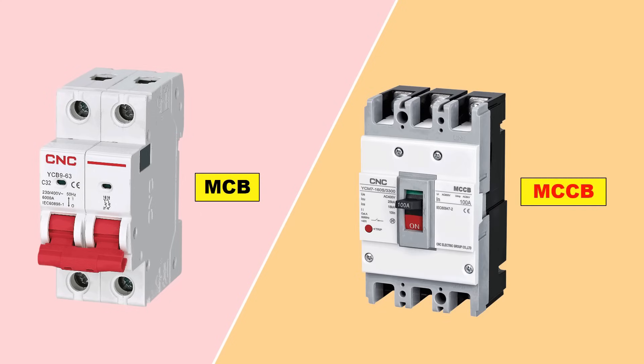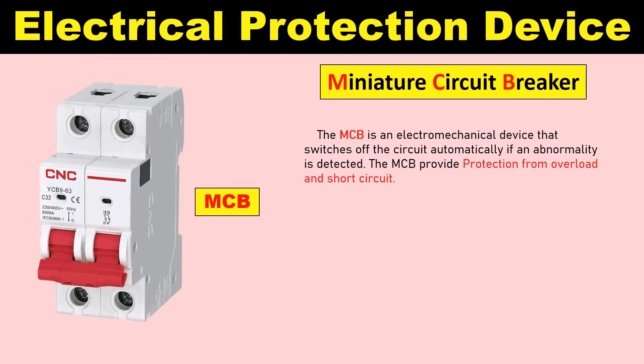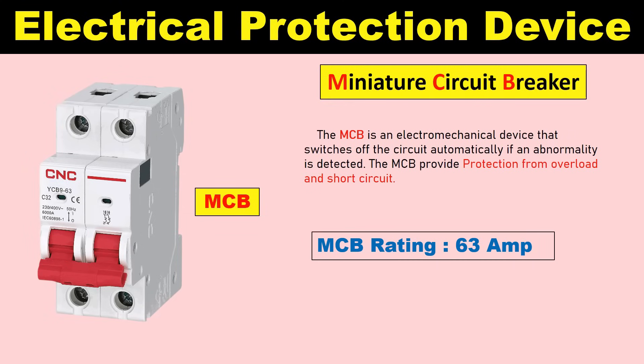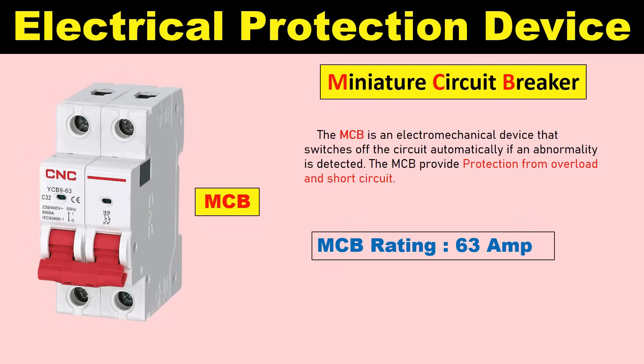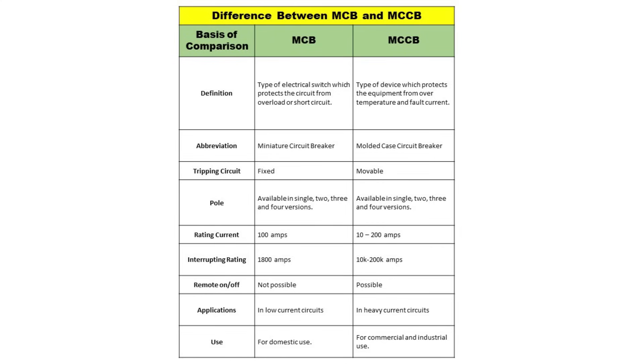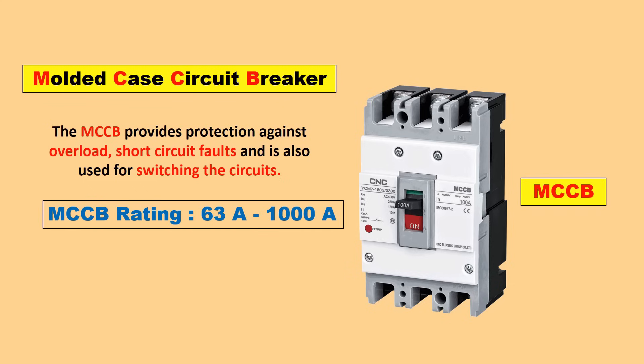Next device is MCCB. Full form of MCCB is Molded Case Circuit Breaker. The maximum MCB rating you can buy is 63A, though these days a 100A MCB is also available. If you want a protection device of even higher rating, you have to buy a MCCB. MCCB also provides protection from overload and short circuit, same as MCB, but you can find a MCCB of 1000A or even higher rating in the market.